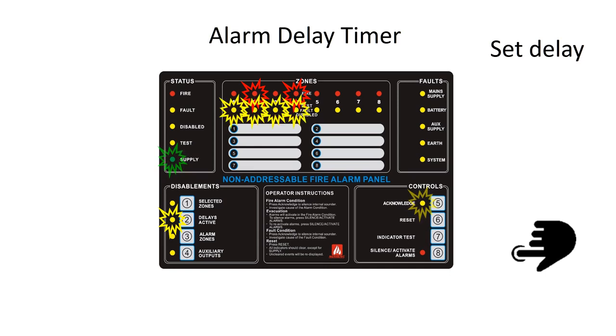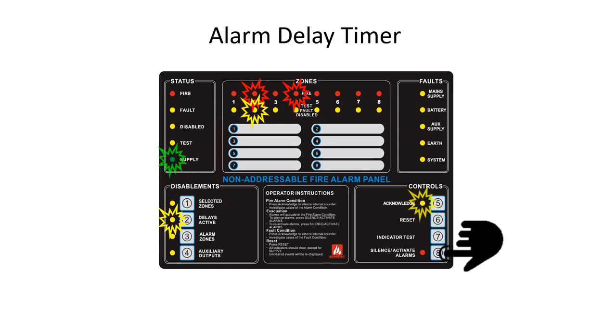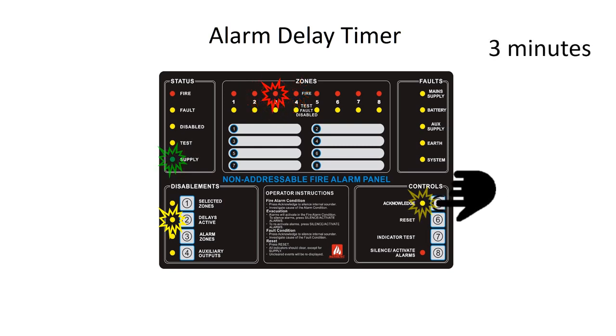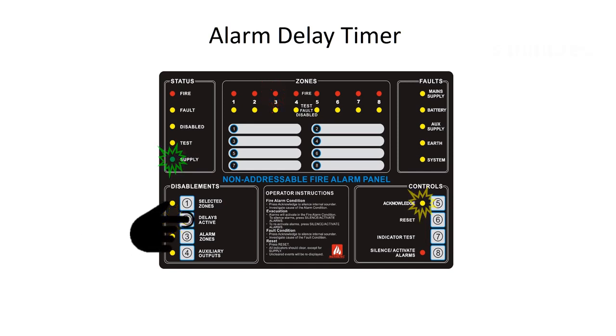The first 4 yellow zone LEDs are used in combination to set the total delay time. Zone 1 indicates a 1-minute delay. Zone 2 indicates a 2-minute delay. Zone 3 a 3-minute delay, and Zone 4 will delay the alarm for 4 minutes. By using a combination of these delays, the alarm delay time can be set for up to 10 minutes in 1-minute increments. Confirm the selection by pressing the Acknowledge button. The delay time will be displayed by the yellow zone LEDs and be copied to the fire LEDs. To exit the delay time configuration, press the Delays Active button. The Delays Active LED, Zones LED, and Acknowledge LED will all be off.